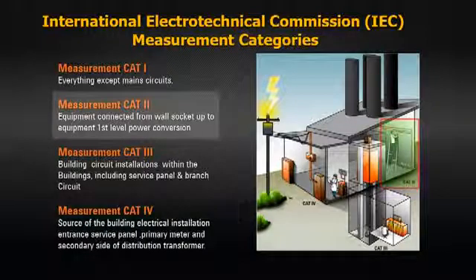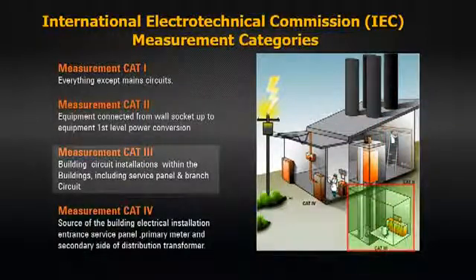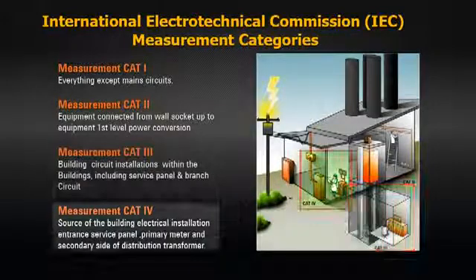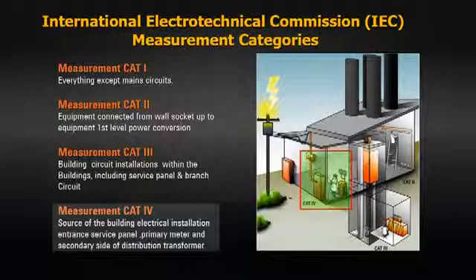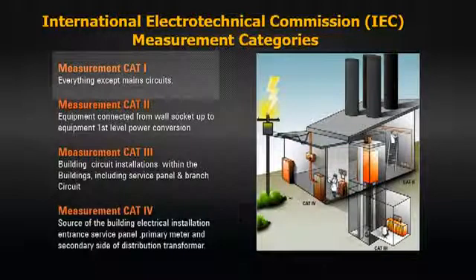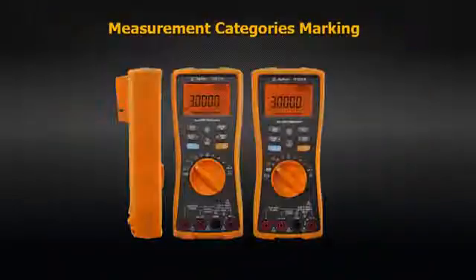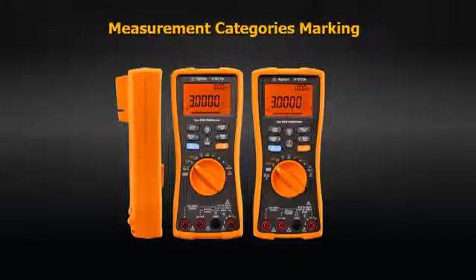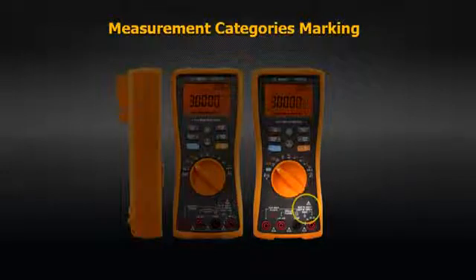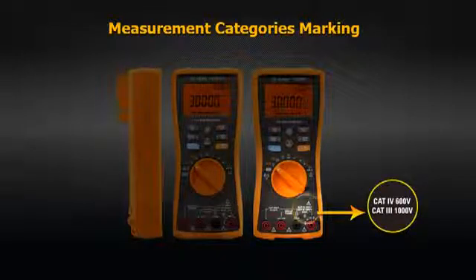Cat 2 applies to equipment connected to the wall socket. Cat 3 applies to building circuit installations that are completely within the building. Cat 4 applies to the source of the building electrical installation. All other circuitry is placed in a separate category called Other or Cat 1. For equipment intended to measure mains circuits, manufacturers are required to mark the rated measurement category on the equipment to indicate the maximum transient the meter can safely withstand.